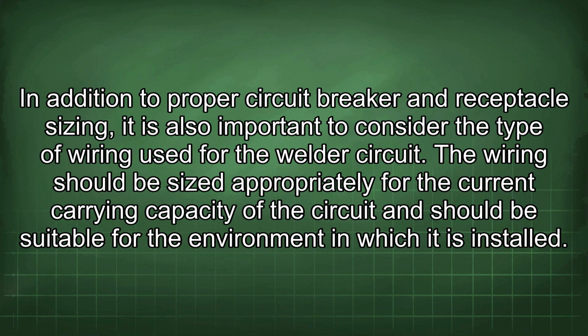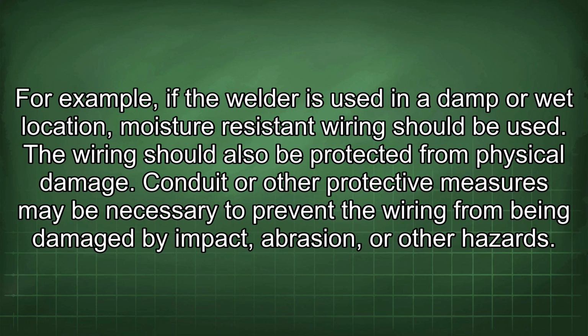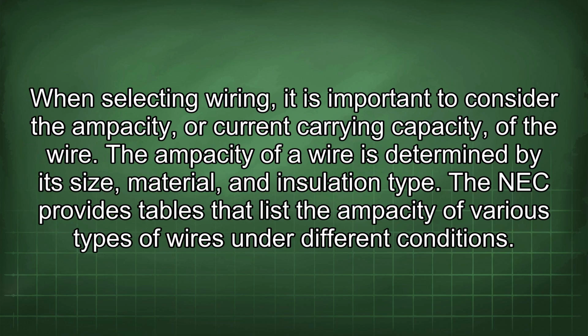be suitable for the environment in which it is installed. For example, if the welder is used in a damp or wet location, moisture-resistant wiring should be used. The wiring should also be protected from physical damage. Conduit or other protective measures may be necessary to prevent the wiring from being damaged by impact, abrasion, or other hazards. When selecting wiring, it is important to consider the ampacity or current carrying capacity of the wire.